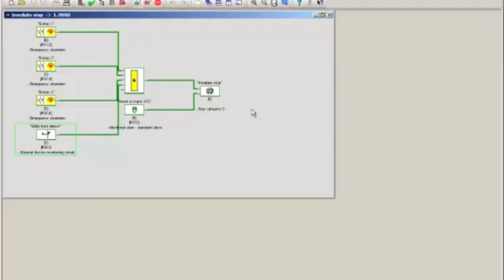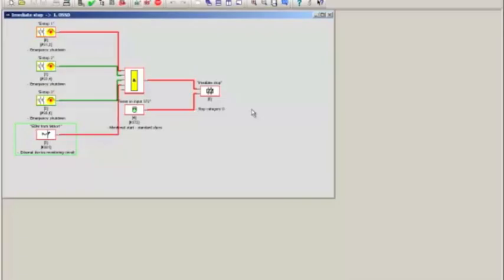Since the EDM feedback is anyhow open right now, really nothing changes. But as soon as I hit an e-stop, that feedback circuit should close, which it cannot do right now because I've disconnected it. And as a consequence, the EDM function block goes into a red flashing mode. I don't know how well that can be seen on the video, but on the actual screen, it's red flashing. This is called a critical fault, and it requires one extra step to reset this.